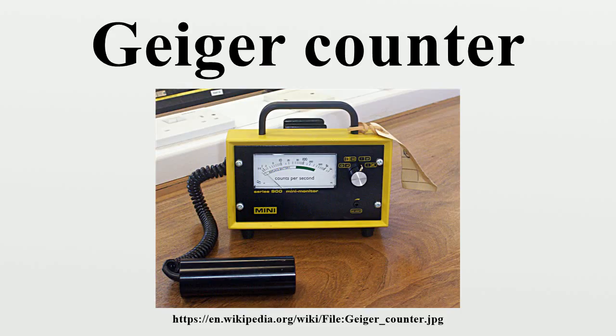apertures or confined spaces. Gamma and X-ray detectors generally use an integral design, so the Geiger-Müller tube is conveniently within the electronics enclosure. This can easily be achieved because the casing usually has little attenuation, and is employed in ambient gamma measurements where distance from the source of radiation is not a significant factor.